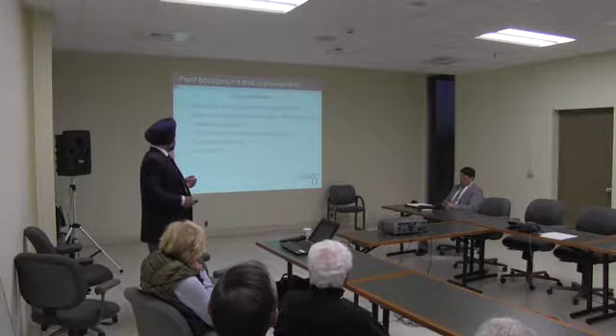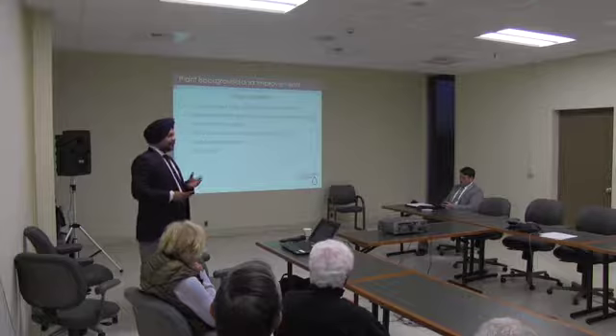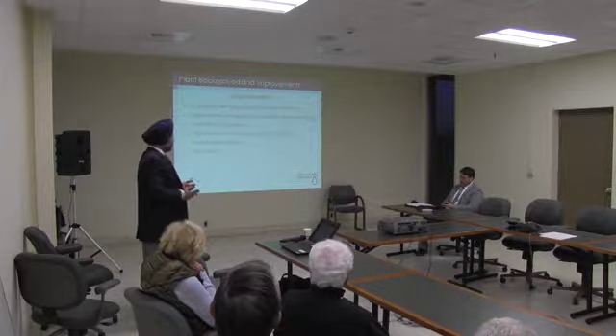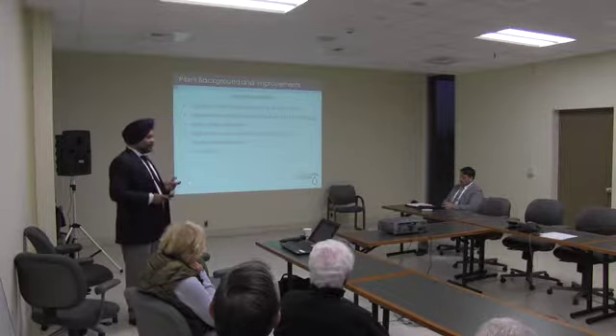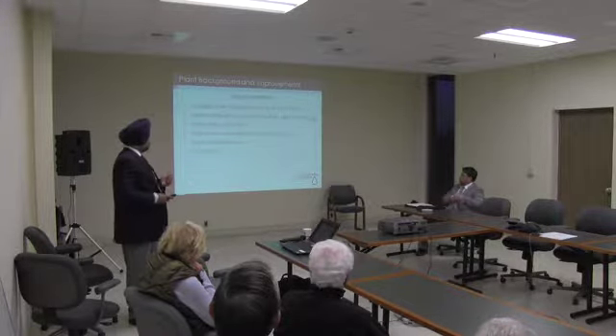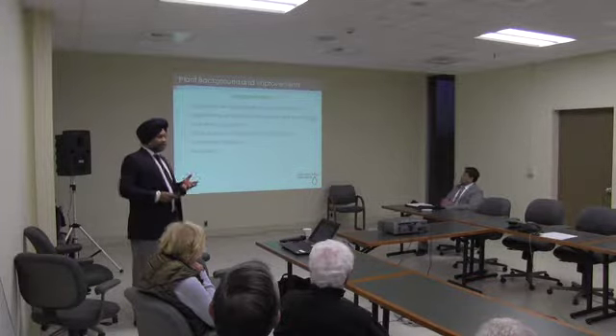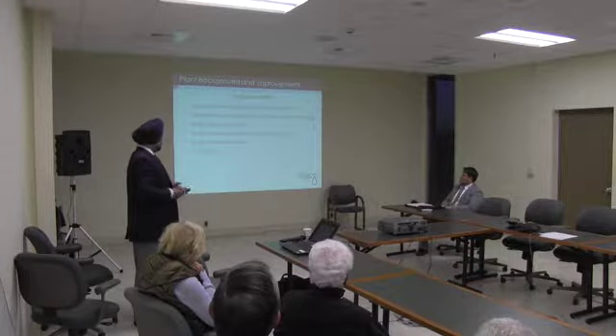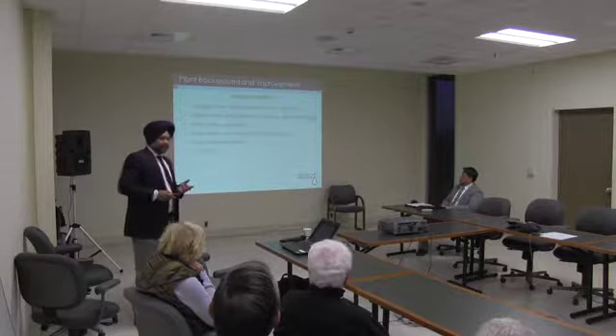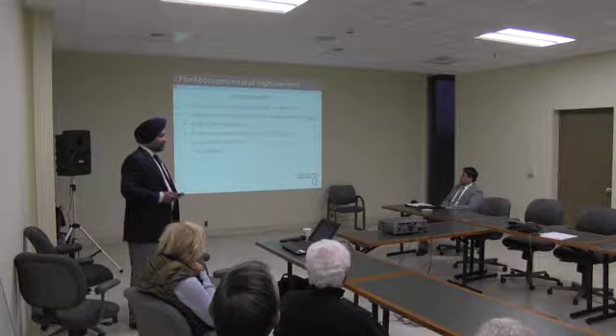So the improvements that are going to be happening under this project, where our plant capacity will increase from 80 million gallons per day to 100 million gallons per day. We will have state-of-the-art treatment processes and technology that will include raw water ozonation. We will have new flocculation and plate settler flocculations. We'll have dual media filtration, and fluoridation will be included as part of this project.